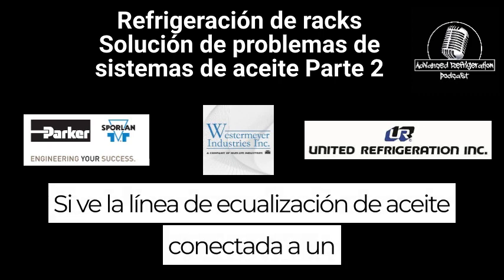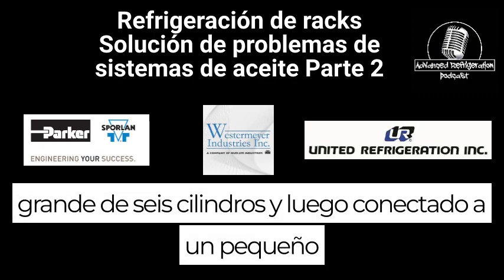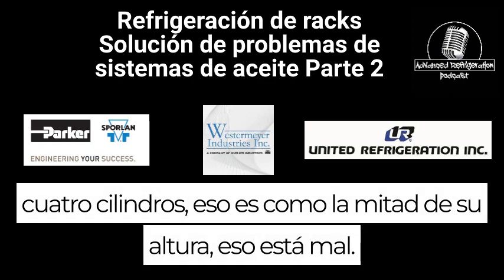If you see the oil equalization line hooked up to a big six cylinder and then hooked up to an itty bitty four cylinder that's half its height, that's wrong.